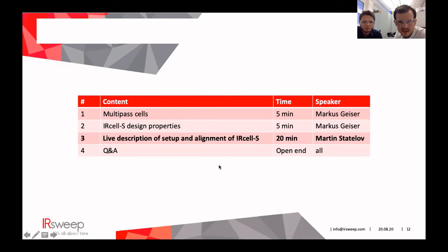How do you adjust and identify different path lengths in a single cell? Is the path length known for each possible path? Yes, good question. Thank you for that. So this is just by choosing which mirror segment you hit first. I think you have the best insight about the design. Yes, that's correct. So by standard, you hit a specific mirror and you get this 15 or 4 meter path length, and then of course both of the cells have different options.